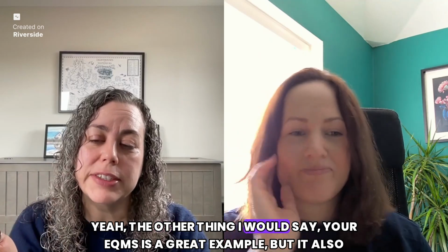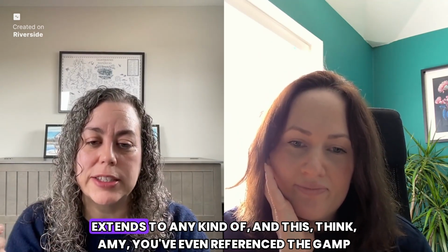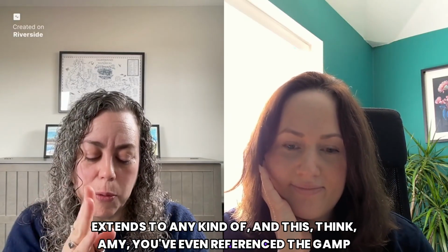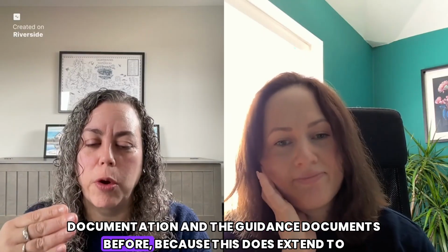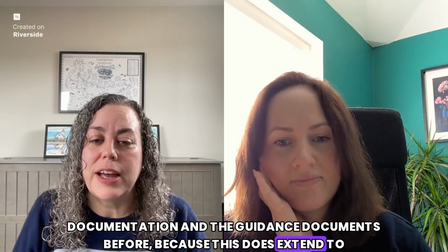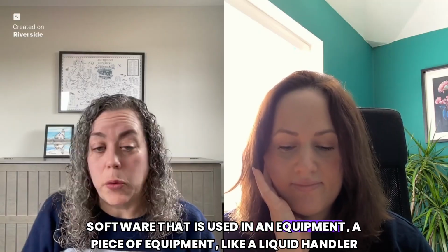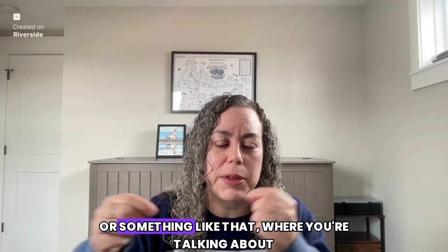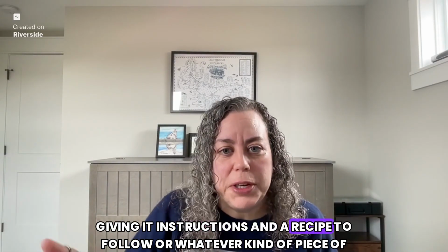Yeah, the other thing I would say, your EQMS is a great example, but it also extends to any kind of software. Amy, you even referenced the GAMP documentation and the guidance documents before, because this does extend to software that is used in a piece of equipment, like a liquid handler, where you're giving it instructions and a recipe to follow.